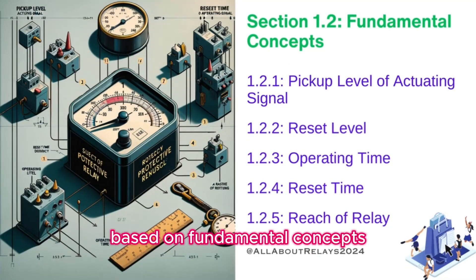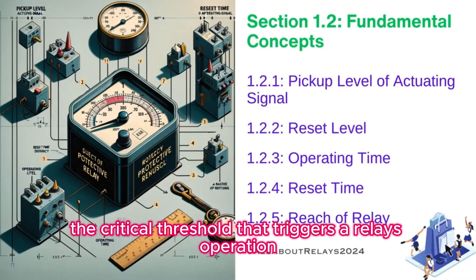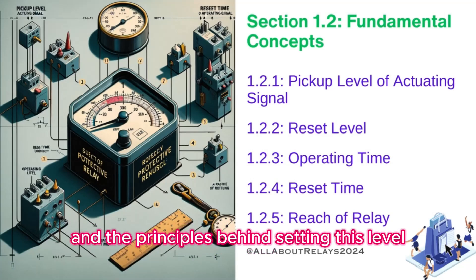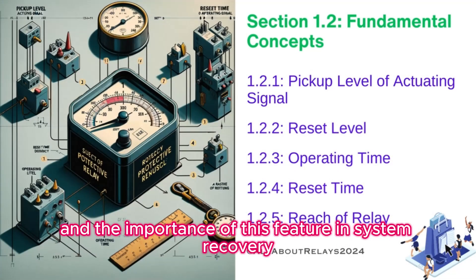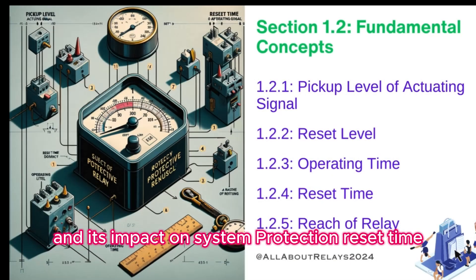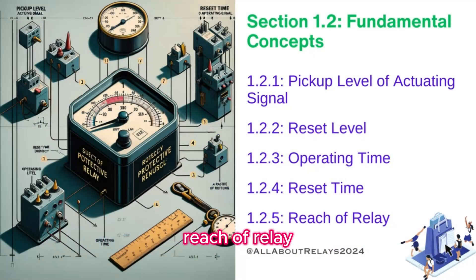Protective relay types based on fundamental concepts. Pickup level of actuating signal: defining the critical threshold that triggers a relay's operation. Reset level: understanding the conditions under which a relay resets or untrips and the importance of this feature in system recovery. Operating time: the time frame from signal detection to relay activation. Reset time: how quickly a relay can return to its normal state post-activation. Reach of relay: distance relays measure impedance to determine the reach within a power system.